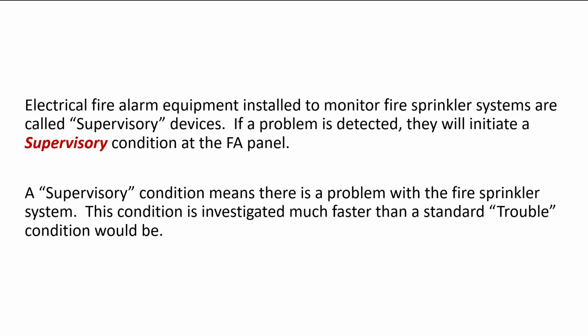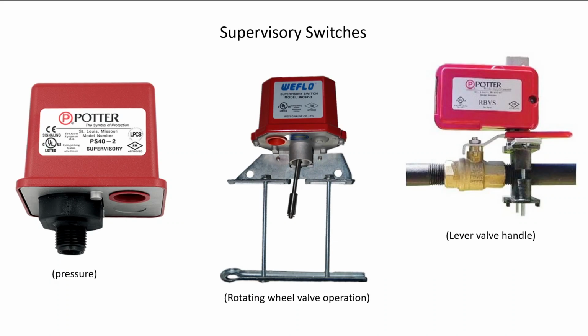Electrical fire alarm equipment installed to monitor fire sprinkler systems are called supervisory devices. If a problem is detected, they will initiate a supervisory condition at the fire alarm panel. A supervisory condition means there is a problem with the fire sprinkler system, and this condition is investigated much faster than a standard trouble condition would be. Supervisory switches are located on any type of manually operated valve, be it a linear valve like we see on the far right, or a rotating valve like the one we see in the middle, and sometimes they are manufactured just to monitor pressures of water or air pressure if it's a dry system.